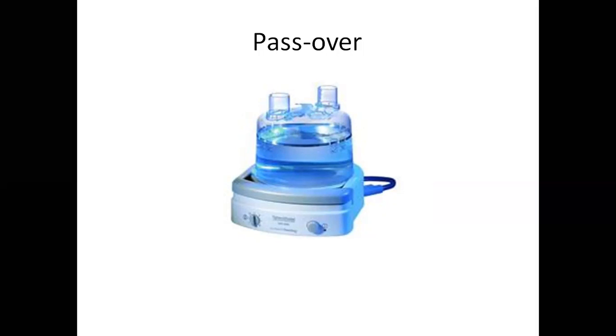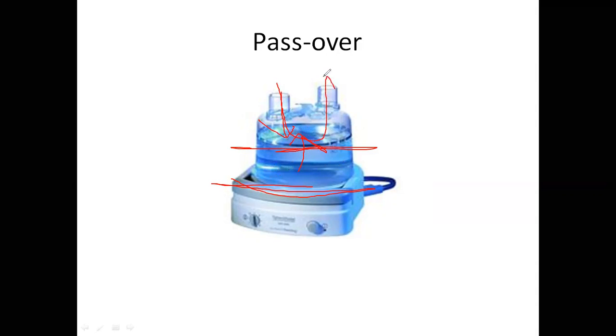Fisher-Paykel uses this particular style of humidifier. This is called a passover humidifier. So when we talk about a passover humidifier, the gas is going to come in this side. This is a heat plate here. There's water in there, sterile water. The gas is going to go in there. We've got heated water here from the heat plate, and what it's doing is evaporating. The dry gas comes in, picks up that evaporated water, and that gas is heated and humidified and passes out that end and flows to the patient.